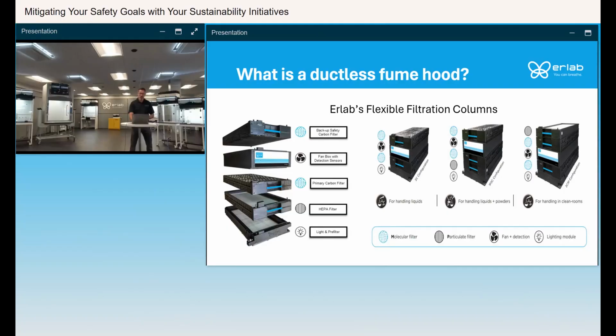So here's a breakdown of our flexible filtration column. You can see in the picture on the left, this is one of our more common filter configurations. Now it's about 50-50. But it starts with a HEPA filter. If you are using any toxic powders, or having any exothermic reactions within your hood, you're going to have that HEPA filter on first. And then you're going to have that primary or main carbon filter. That is what is capturing all the chemical vapors and fumes that are generated within the enclosure.